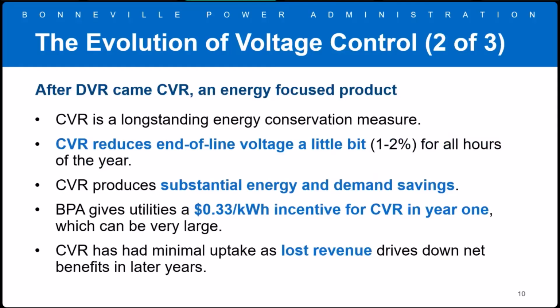This evolved into conservation voltage reduction, or CVR, an energy conservation measure BPA has offered for many years—as long as I've been at BPA, which is 15 years, and I believe quite a long time before then. This is a more modest voltage reduction, basically 1 to 2%, but it's implemented at all hours of the year. It produces substantial energy and demand savings, and BPA provides a very attractive incentive of 33 cents per kilowatt saved. This is only provided in year one, though it's a large incentive. We assume utilities will implement this voltage reduction in a perpetual fashion—it's intended to be long term.